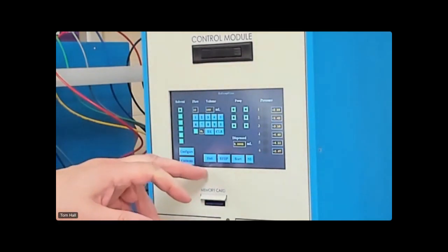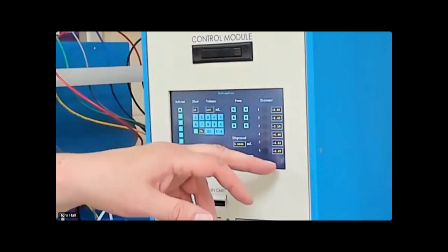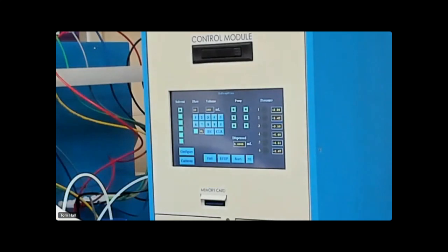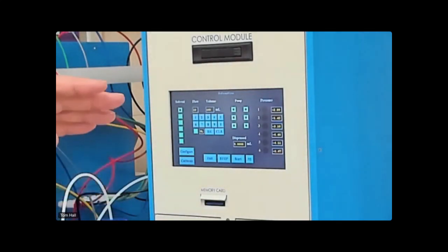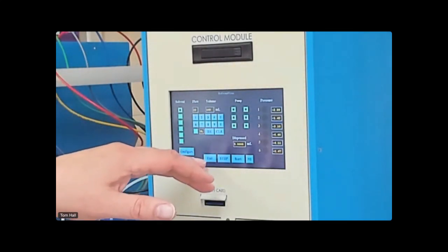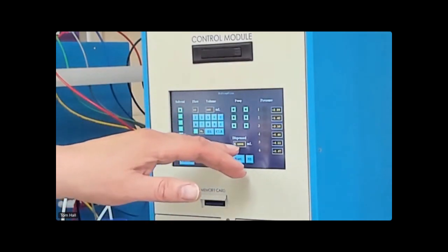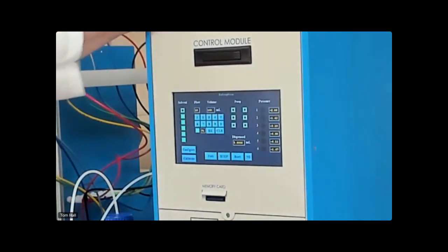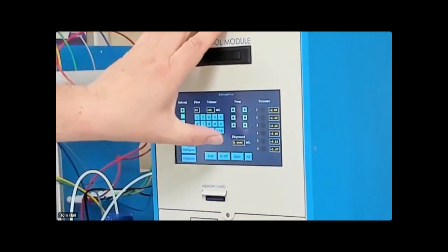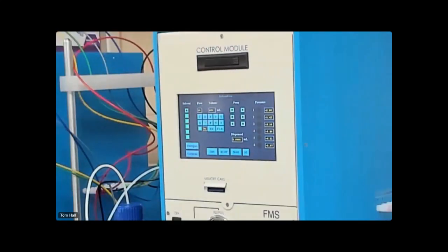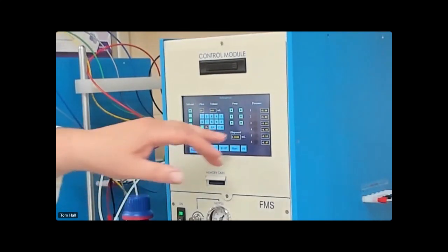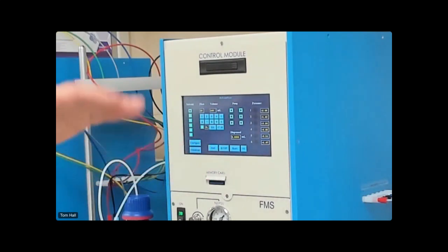There's a stop and hold function. The hold function is actually important. It has a built-in alarm for overpressurization, which you can reset here on the right. And if you hold the step, then it will just stop at the already dispensed volume. And if you resume it, then it will just go on. So you don't have to do any calculations in your head about how many mils you already dispensed. If you press stop, it's reset to 0. If you press hold, it won't be reset, and it will just resume the step that you're working on. We'll just show the reset button again.